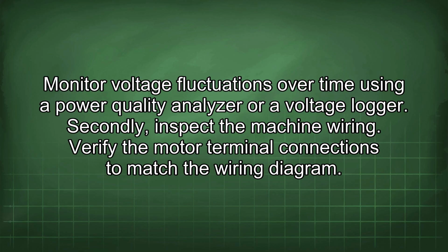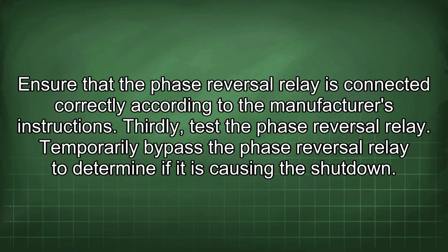Secondly, inspect the machine wiring. Verify the motor terminal connections to match the wiring diagram. Ensure that the phase reversal relay is connected correctly according to the manufacturer's instructions.